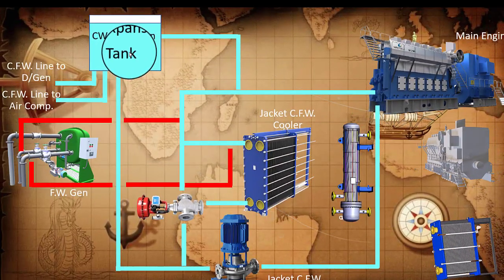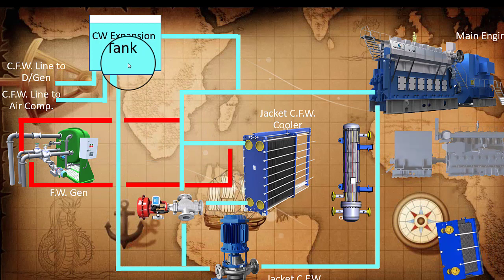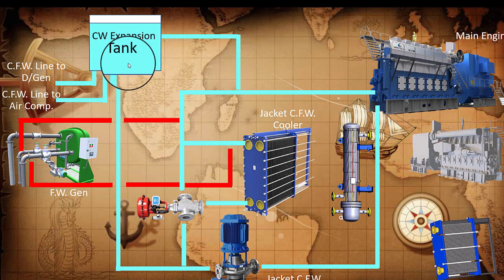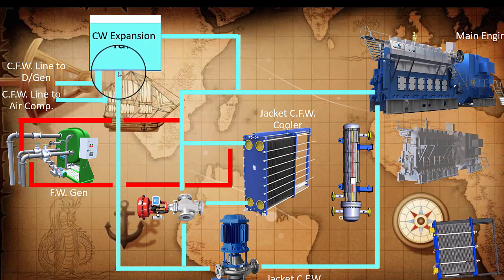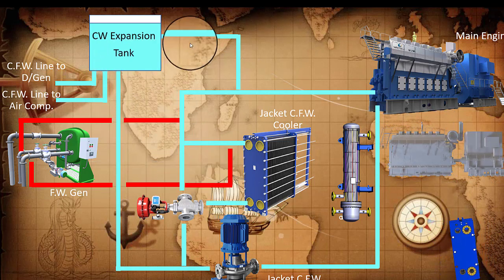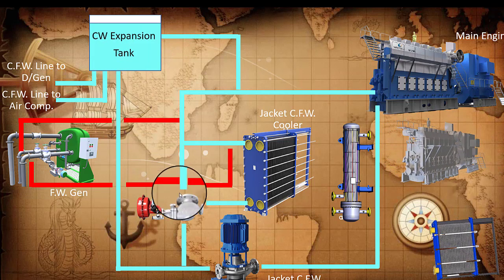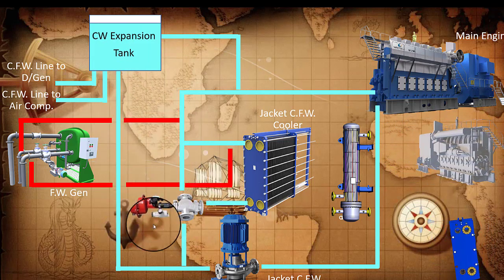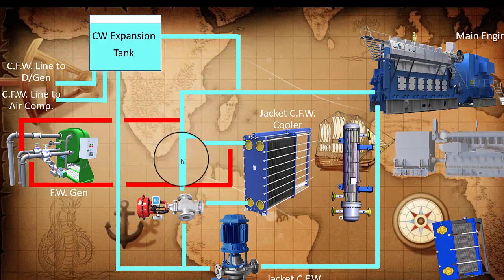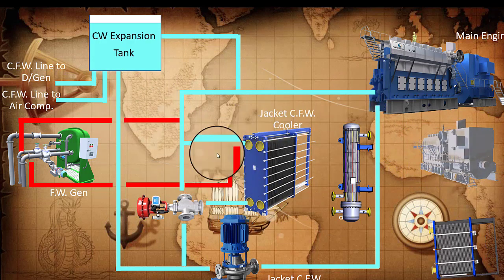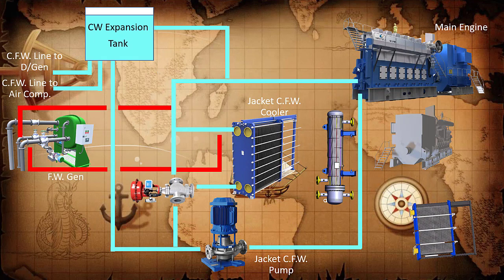The expansion tank, as you can see in this diagram, compensates for heat loss through the closed circuit loop. It is also the storage where the fresh water medium is put in and refilled from time to time, and it absorbs pressure increases due to thermal expansion. The temperature control valves mix the fresh water from the expansion tank with the water circulating through and out of the main engine.